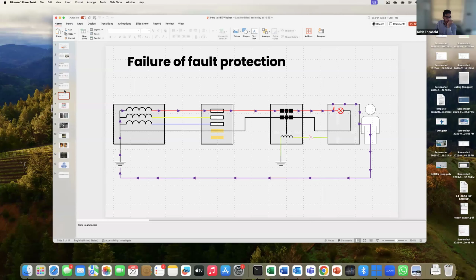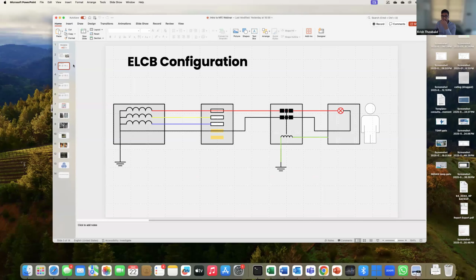So Abhijit, it's a good question. Irrespective of whether it is a voltage operated device, a current operated device, an RCD or an ELCB, when you perform a test for earth fault loop impedance, it can cause a trip. The first thing is, if you have an ELCB, please remove it. They're not permitted by the standard anymore. The standard requires you to use a device that conforms to IS 12640 or IEC 62423. So there is no option of using an ELCB. Now, the way a test instrument works is that it injects a current through the line conductor and the protective conductor. This current will obviously be picked up by the ELCB or RCCB.